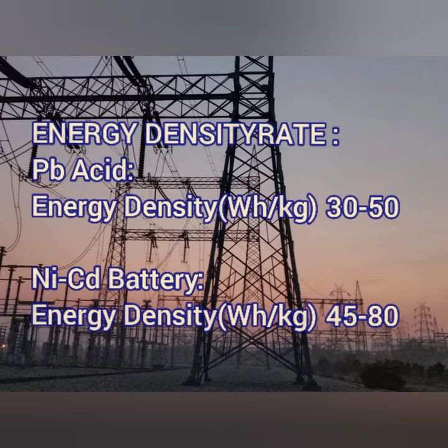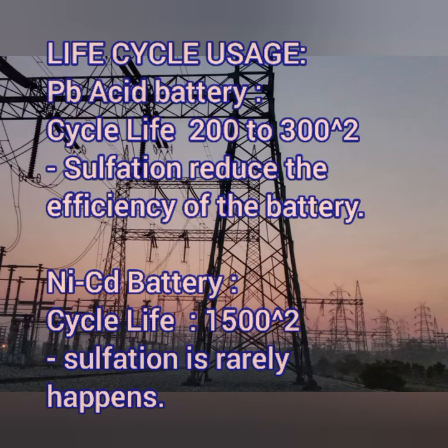Next is life cycle usage. Lead acid batteries may have 200 to 300 cycles per cell, meaning the discharge and recharge capacity is up to 200 to 300 times per cell. In nickel cadmium, it is about 1500 cycles per cell — charging and discharging can be done up to 1500 times.